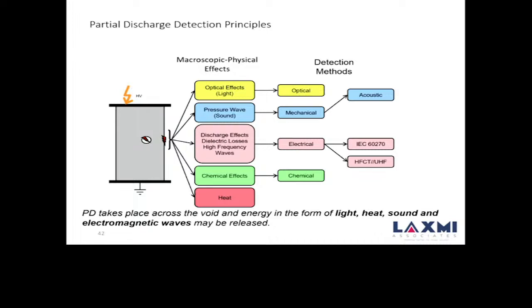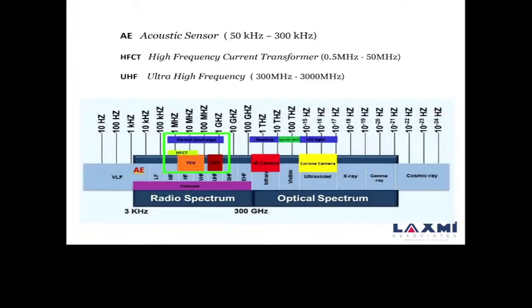Then you have radiation, because it is movement and gives some kind of collision, so you have radiations in megahertz and gigahertz. Those radiations are captured by sensors. Then the chemical effect, which is the DGA, where you can get information about the partial discharge. Then heat, which is very usual in thermography, where you can see a hotspot. Those are the impacts of partial discharge, and the way you can derive that a transformer has a partial discharge is by combining all these methods and knowing about those things.